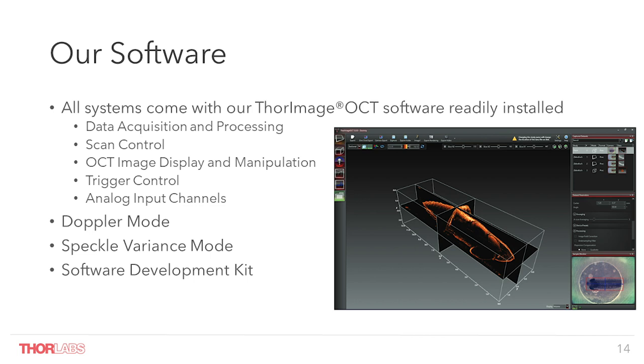With our new spectral domain OCT base units you also have full flexibility in terms of triggering — you can bring in external triggers or use our system as the master. On top of that, you can bring in analog signals, for example from a fluorescence detector, to facilitate multimodal imaging with other imaging techniques. Also included are options for Doppler analysis and our angiography mode, which we call speckle variance. If you need something more advanced, you can also use our software development kit, which can be programmed either in C or in LabVIEW.